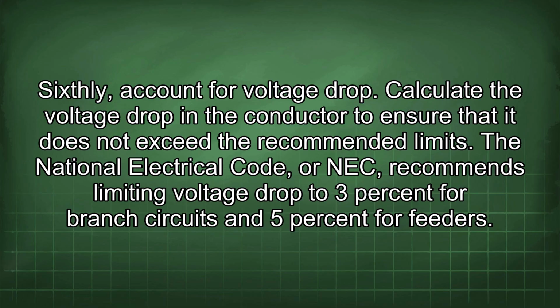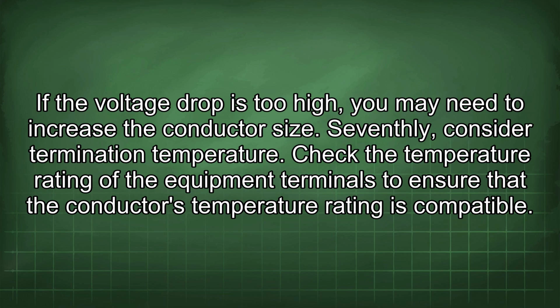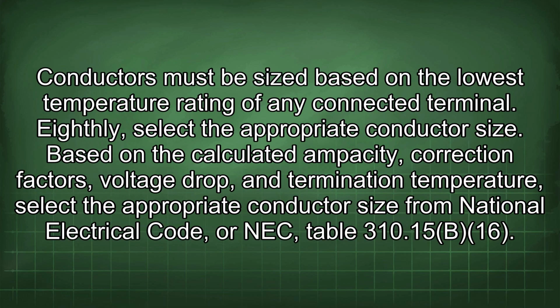Sixthly, account for voltage drop. Calculate the voltage drop in the conductor to ensure that it does not exceed the recommended limits. The NEC recommends limiting voltage drop to 3% for branch circuits and 5% for feeders. If the voltage drop is too high, you may need to increase the conductor size. Seventhly, consider termination temperature. Check the temperature rating of the equipment terminals to ensure that the conductor's temperature rating is compatible. Conductors must be sized based on the lowest temperature rating of any connected terminal.